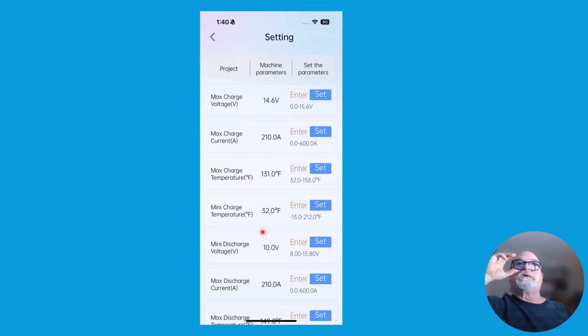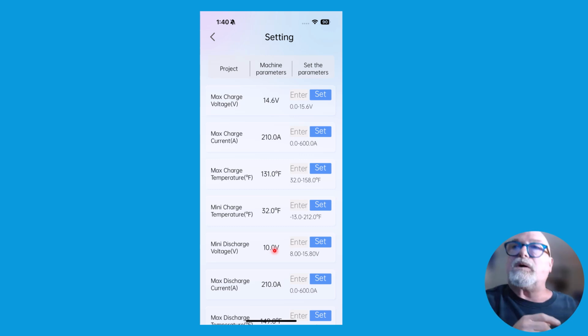I do not recommend that you change any of these. My battery may not be locked because I'm a partner of theirs, I don't know, but I can go in and change these - I do not recommend it. The only one I'd recommend changing is the low voltage cutoff - I set mine at 11.2, click enter, put in 11.2, then hit set. There's no energy left beyond 11.2 anyway, so why go down to 10 volts? No need. Don't touch any of the others - leave 14.6 as your max charge voltage and you'll be fine.